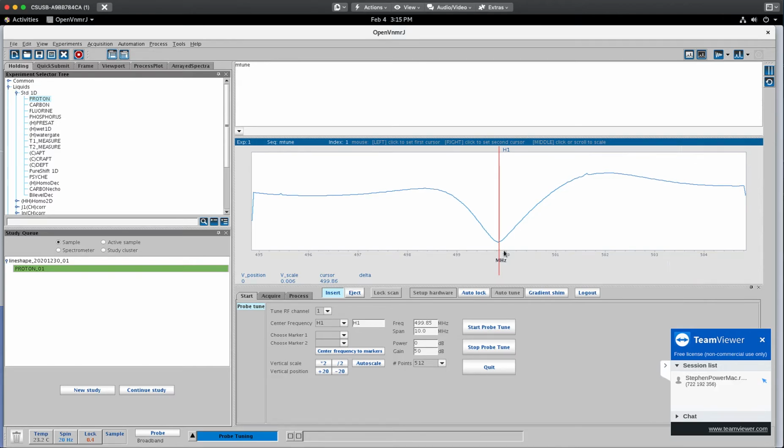So I went into the NMR room and adjusted the capacitor and the barrel and the knob. And now you can see that the dip is on the red line. I could still tune it some more because you can see there's some distance between the baseline and the dip. But there wasn't a sample in there, so I'm just not going to tune it any further.